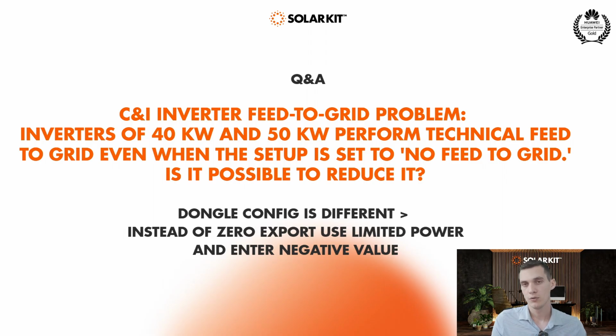And if you go to this limited power output, then you set, for example, in this size, I think the best option would be to start with negative 1 kilowatt or negative 0.8 kilowatt. And I think you will see that the feed-in would stop immediately. Then you can start to reduce this number, like with 100 watt steps, and see where the feed-in is realized and which one was the limit.